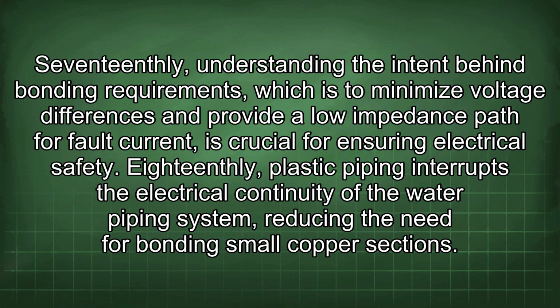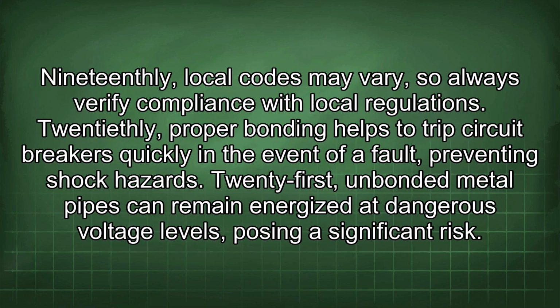18th, plastic piping interrupts the electrical continuity of the water piping system, reducing the need for bonding small copper sections. 19th, local codes may vary, so always verify compliance with local regulations. 20th, proper bonding helps to trip circuit breakers quickly in the event of a fault, preventing shock hazards. 21st, unbonded metal pipes can remain energized at dangerous voltage levels, posing a significant risk.